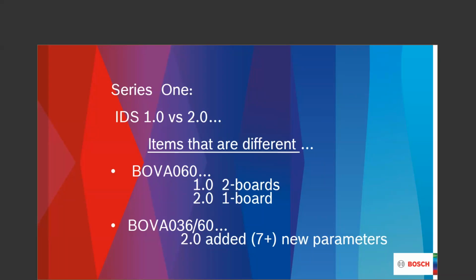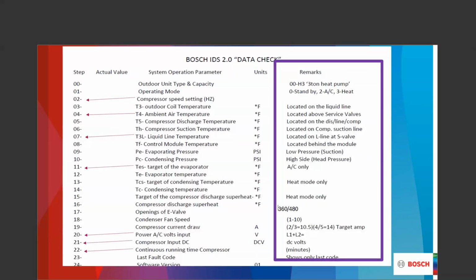The BOVA036/60 on the 2.0 has 7 new parameters. Those parameters are shown in the data checklist in the IOM. Now we have the capability of pushing a parameter button and actually seeing the compressor operational Hertz rating. We couldn't see that with the 1.0. You would have to wait the 20 seconds and let it go back into the LED screen to show you that. Now we can just push a button.